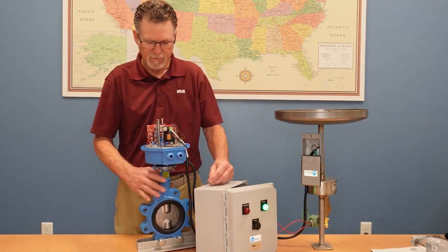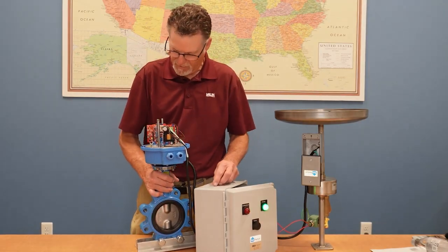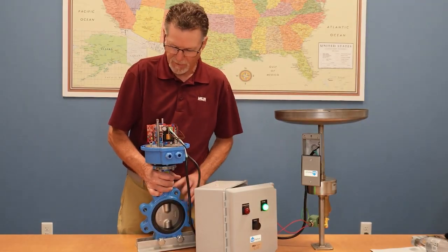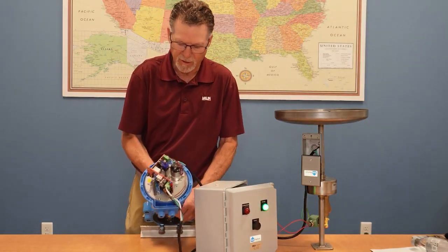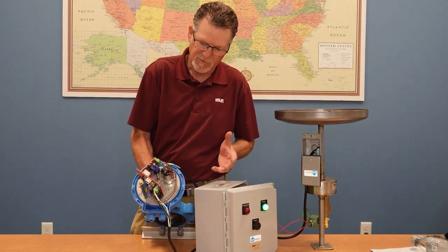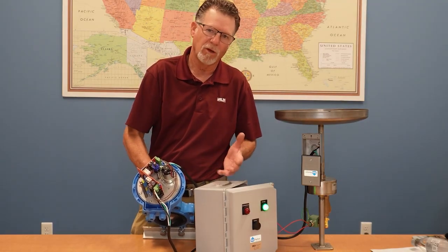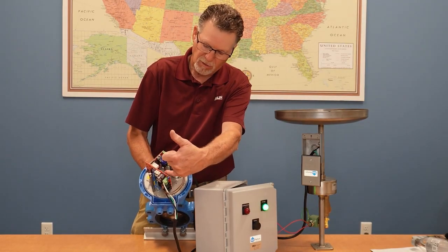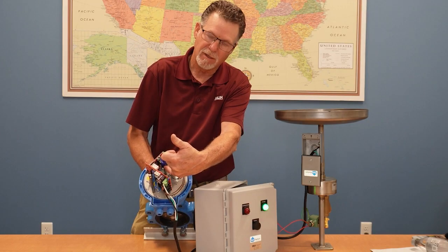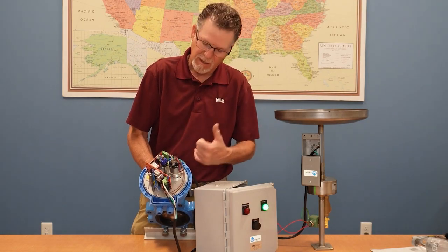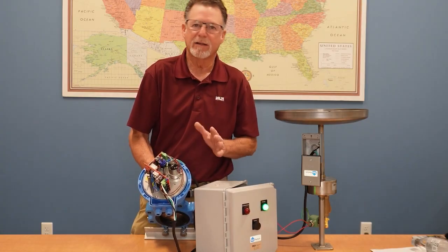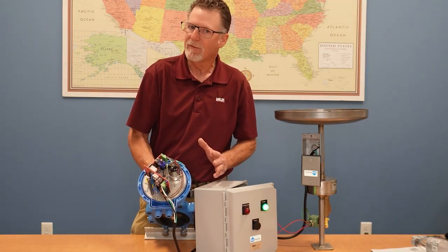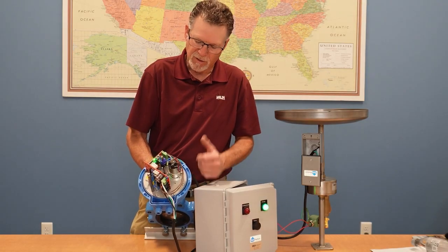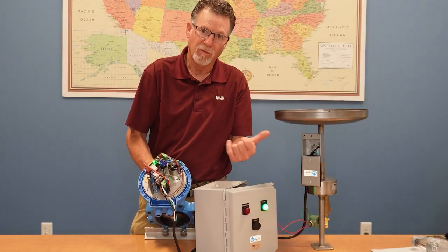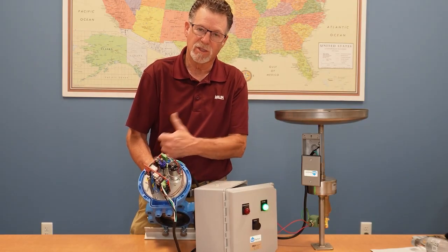As far as the valve itself, there's not much you need to do with it or check, but if it's not fully closing or fully opening, there are cams here that trip limit switches, and they are adjustable. They're set at the factory, so you shouldn't have to adjust them. But there's one for full open and full close, which stops the motor.